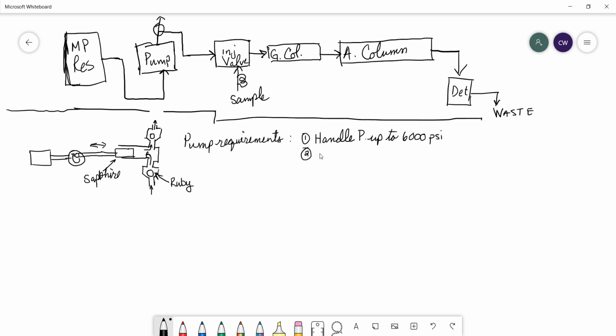We need a pulse free output, right? Because we don't want our pressure changing. So there's a few different designs for this. A lot of times, this single cam pump head is repeated at least 2 to 4 times in a single pump, so that when one pump head is on the reverse stroke, the other pump head is on the forward stroke. That way the pulse dampening is minimized. And then on top of that, they go into a pulse dampener.